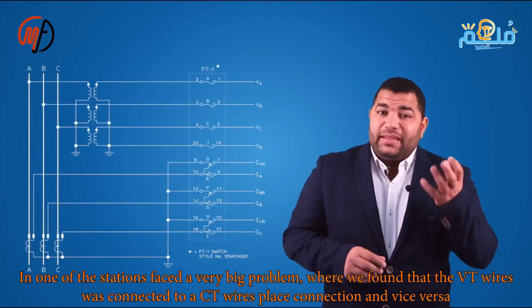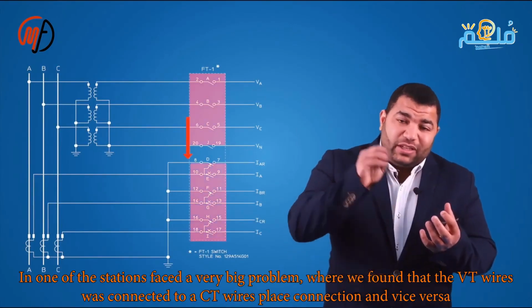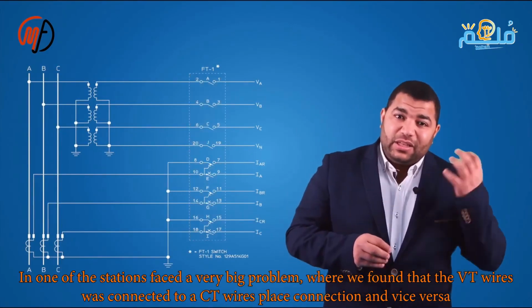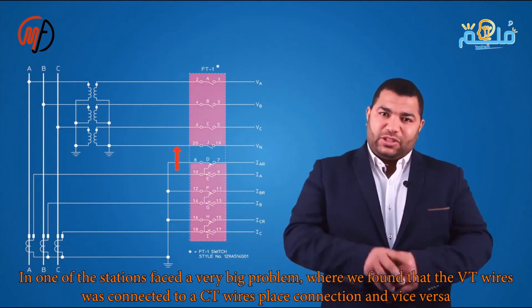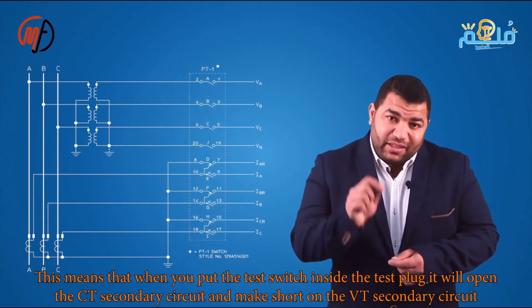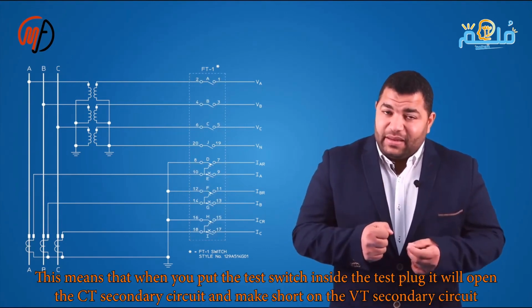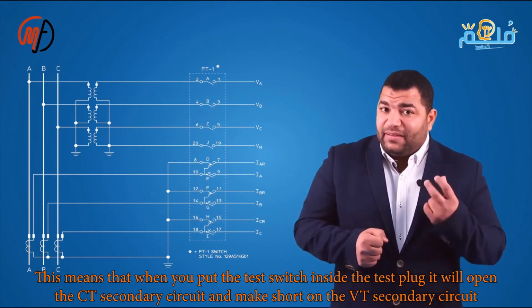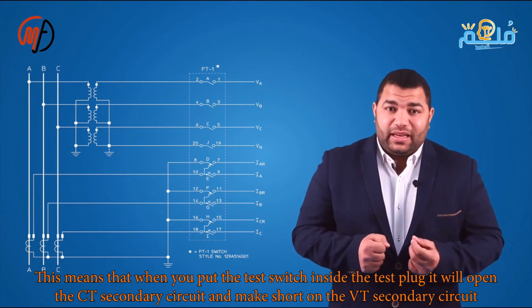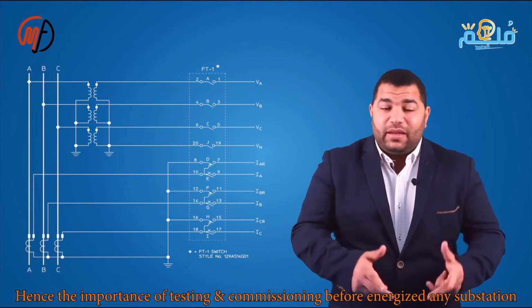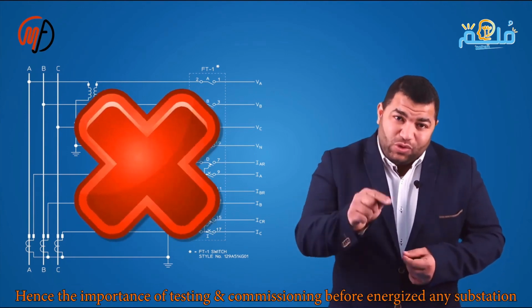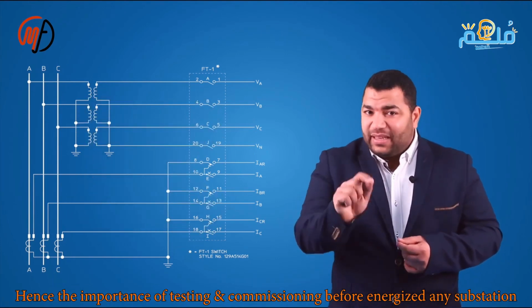We found that the VT wires were connected to the CT location in the test switch, while the CT wires were connected to the VT location in the test switch. This means that when the test switch is placed inside the test plug, it will create an open circuit for the CT and a short circuit for the VT, which is very dangerous. This highlights the importance of testing and commissioning before operating any station.